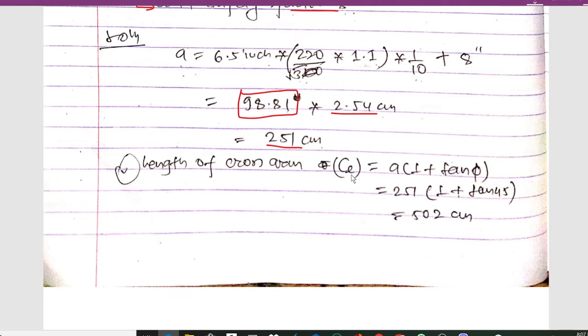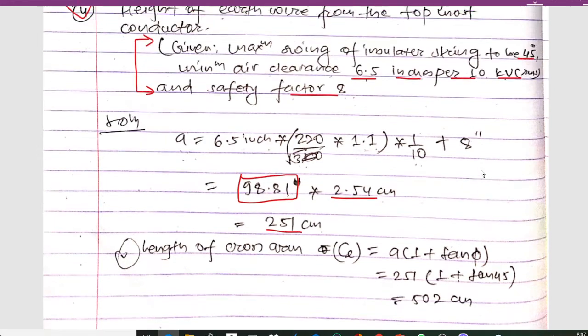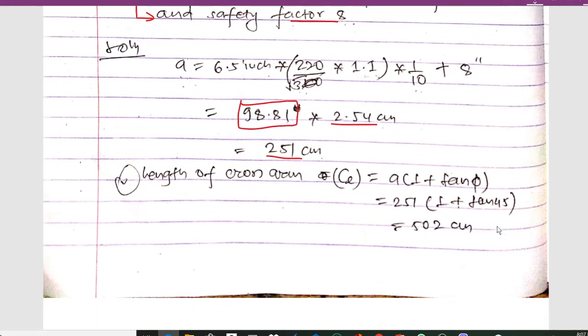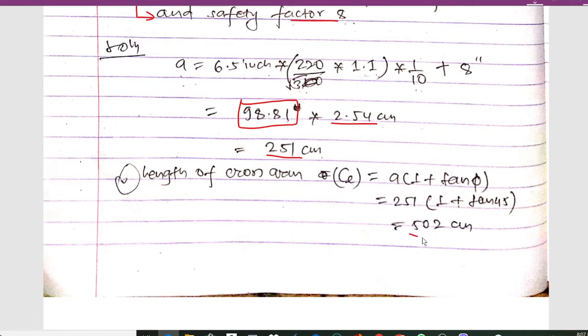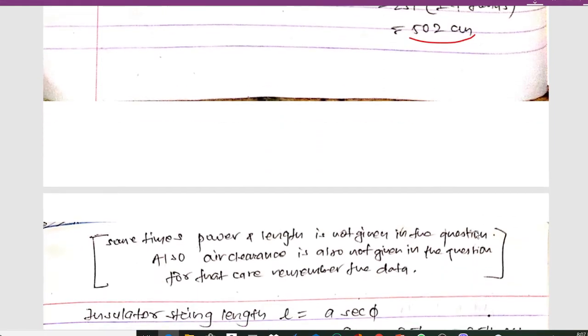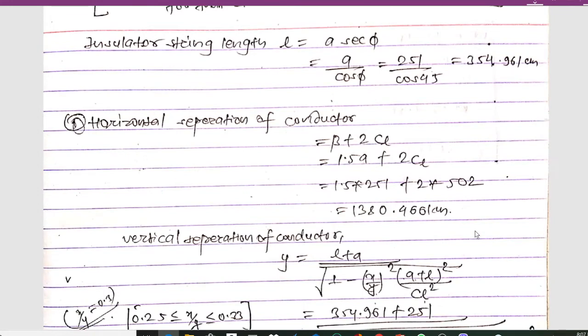To calculate the cross arm length CL, we use the formula: CL = A × (1 + tan φ). With A = 251 centimeters and φ = 45 degrees, we get: CL = 251 × (1 + tan 45°) = 251 × 2 = 502 centimeters.